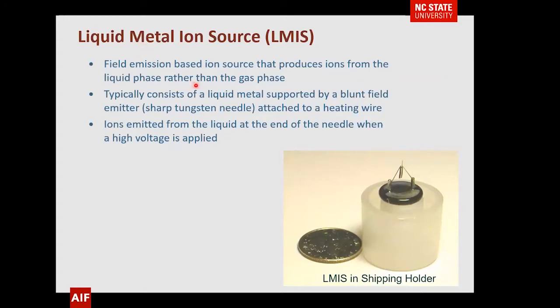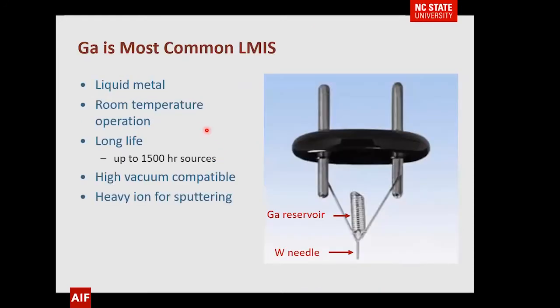The liquid metal ion source is a very interesting source. It's a field emission based ion source that produces ions from the liquid phase rather than the gas phase. It's a liquid metal supported by a tungsten needle. Here's an example of one — you can see it's not much bigger than, actually smaller than, an American dime. Here's your needle and the electrodes. The ions are emitted from the liquid at the end of the needle when you apply a high voltage. Gallium is the most common liquid metal ion source — it has properties that are very suitable for what we want to do.